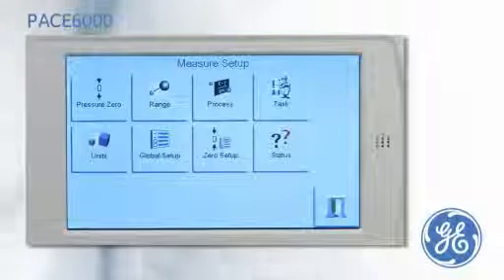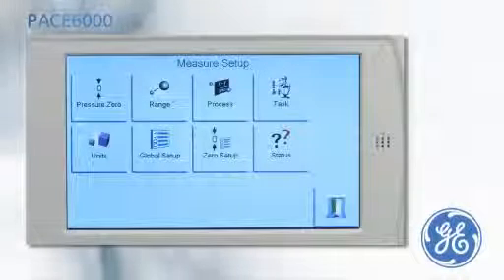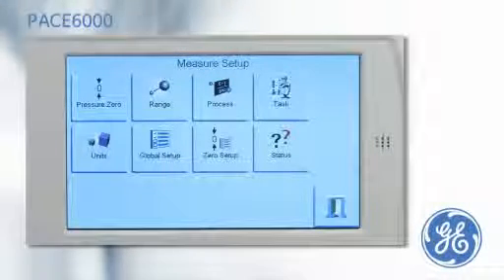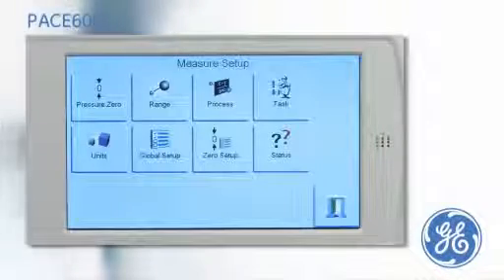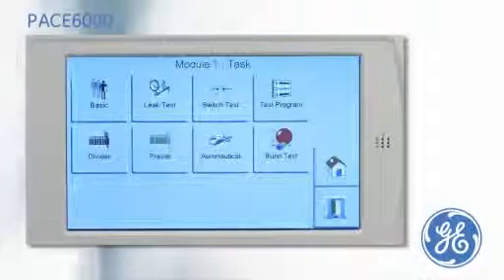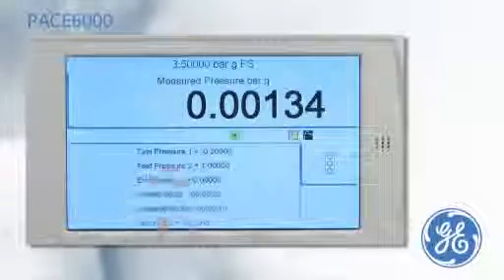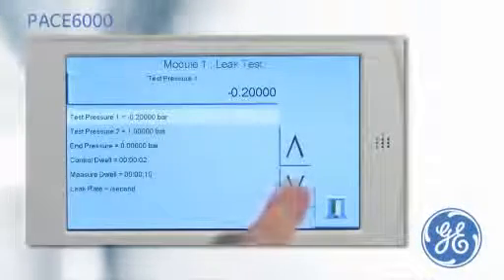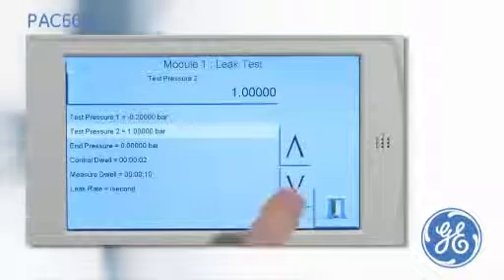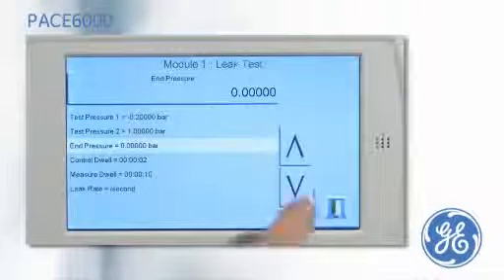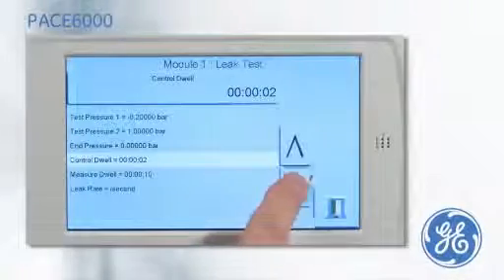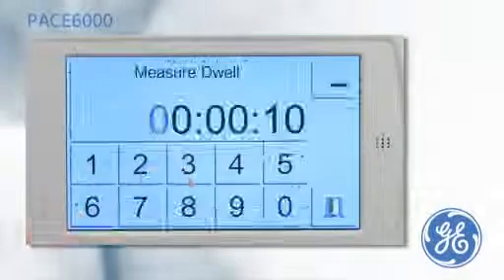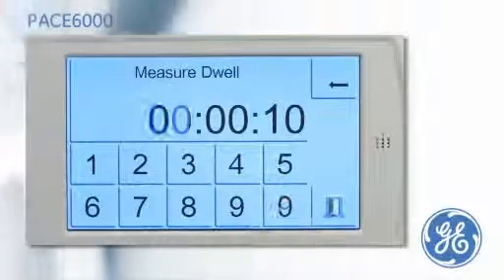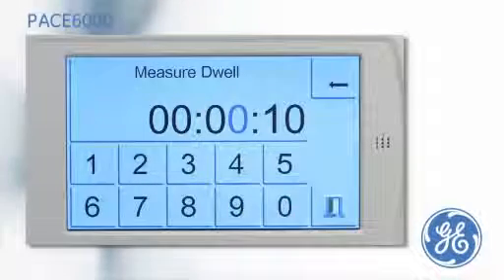To test for leaks in the test system, or to ensure there are no leaks in a device under test that has been dismantled and reassembled, the PACE6000 has an optional leak test task. Both a negative test pressure and a positive test pressure, along with the control dwell, can be entered. The leak test time, called measure dwell, is entered in hours, minutes and seconds.